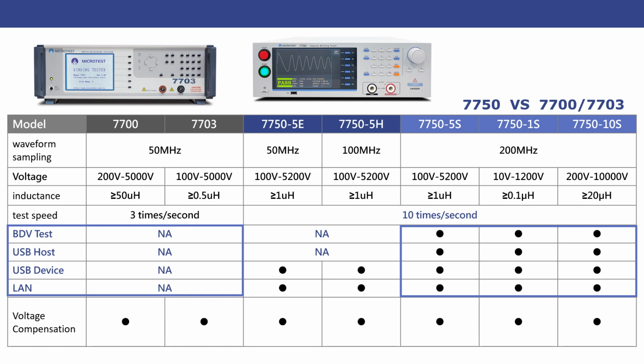The table below illustrates the improvements in the new generation of the 7750 impulse winding tester compared to the old model. Increased testing speed to 10 tests per second. Addition of breakdown voltage testing. Addition of USB and LAN interface. Introduction of second-order differential comparison mode to meet the measurement needs of one-piece mold inductors.